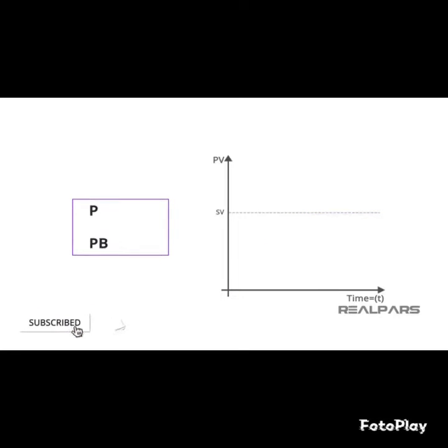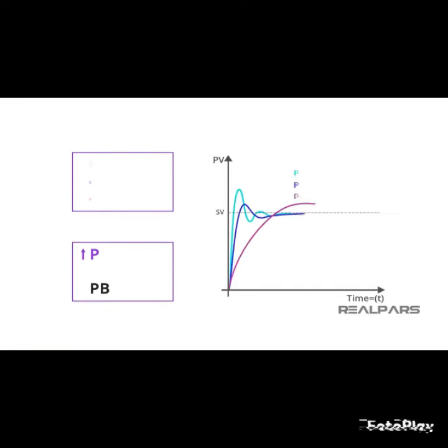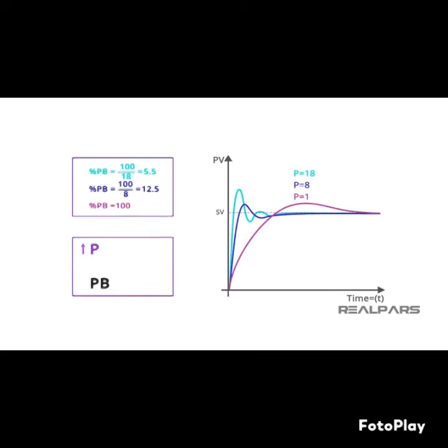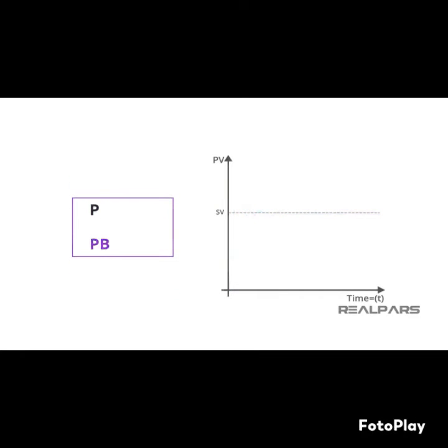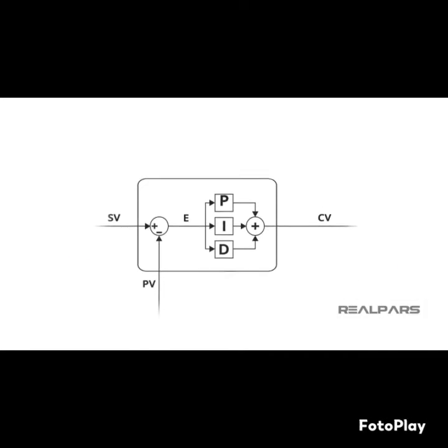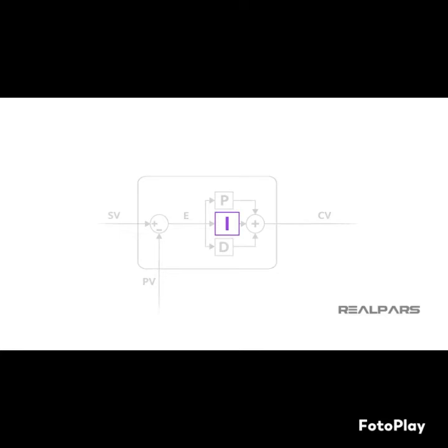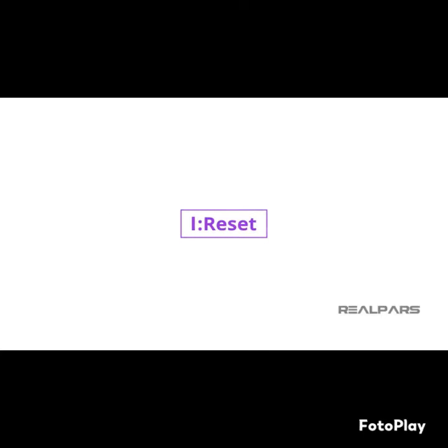For controllers that use the term gain, adjusting this tuning parameter higher may cause more sensitive, less stable loops. Conversely, on controllers with proportional band units, decreasing this tuning parameter affects the loop in the same manner. Keeping this in mind, knowing the type of controller you have is essential to ensure that you are properly adjusting your parameters.